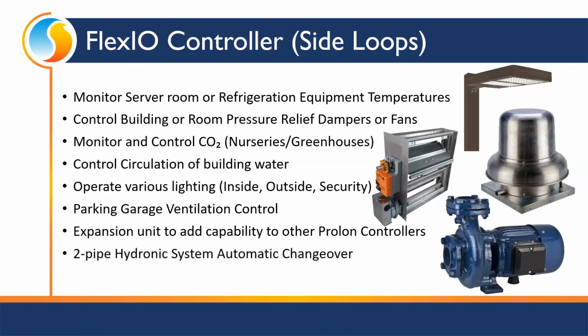We've done two-pipe hydronic system automatic changeover. So on a two-pipe system, you've got boilers and you've got chillers, but only one or the other runs at any given time. And we have to decide based on, is it hot out, is it cold out, what do we need? Do we need hot water or cold water? And we can do the changeover between those automatically. And of course, anything else that needs to be on an automatic schedule.